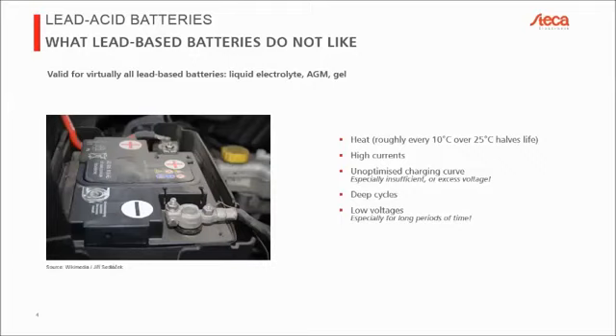The second point after heat is that lead batteries do not like high currents typically. There are some exceptions, notably the car battery, which is actually manufactured to provide high currents. But in the vast majority of cases, especially stationary batteries used in PV off-grid systems, high currents are detrimental to the battery. Typically the higher the current you demand from a battery, whether discharging or charging, the shorter the life expectancy.